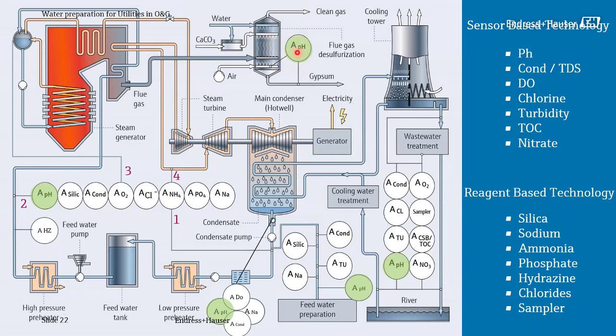Also here you want to measure pH. And then finally, after the cooling tower and after wastewater treatment, before the water gets discharged back to a river or to a water body, again pH is of interest. So pH is, I would say, one of the most important parameters in this process. Conductivity is the second one, it gives you an idea about all the impurities, salts, all that stuff you don't want to have in this process. So conductivity should be very low.